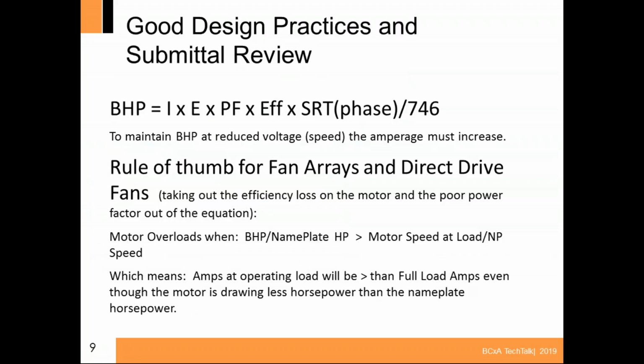When I look at these and I'm looking at design practices, we go back to the VFD idea, where the motor voltage is actually lower at slower speeds. So to get the same brake horsepower, you have to increase the amperage. I'll give an example. Let's say you have a 10 horsepower motor that's pulling 9 brake horsepower, operating at 1,140 RPM. The motor inside it is a 1150 RPM motor, it's direct driven, and it has a variable frequency drive.